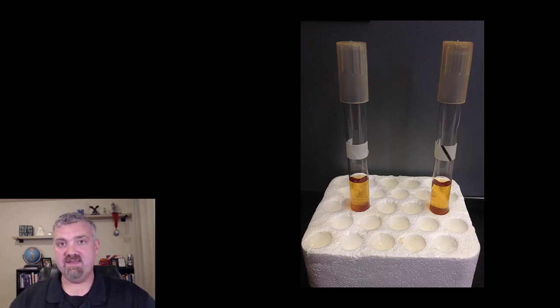The problem is we can't look at this and say, okay, we sterilized what was inside the autoclave, because it doesn't tell us how long the autoclave reached that sterilizing temperature. If you really want to know if an autoclave is working, you use what are called biological spore tests where you put like paper or liquid or something that has a really hardy spore in it.